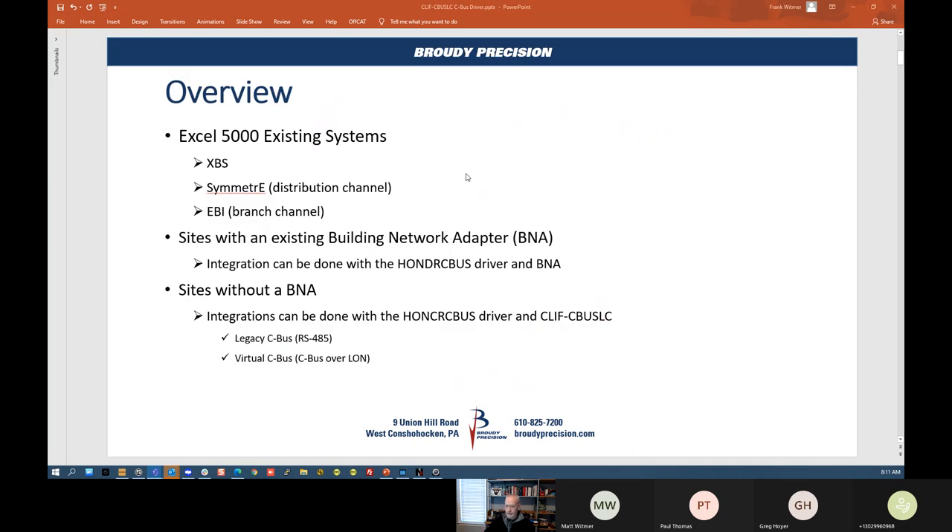What we're talking about is existing XL5000 systems, whether it's systems out there with XBS as a front end, Symmetry, or EBI. We're all using the legacy XL5000 devices. So what we have is systems where you have CBUS on a metallic pair RS-485, or it could be LAN-based CBUS over LAN. In some cases, sites have a Building Network Adapter, a BNA, bringing CBUS over IP into Symmetry or EBI or whatever the front end was. And there are also sites without the BNA, which are brought directly into a 485 port.